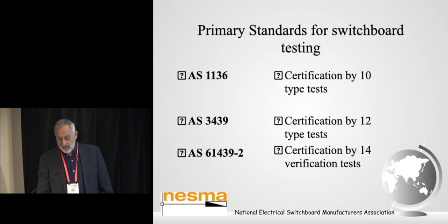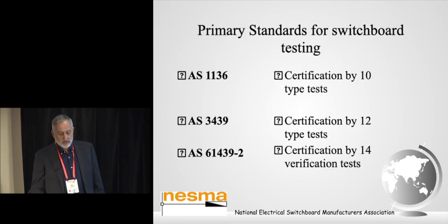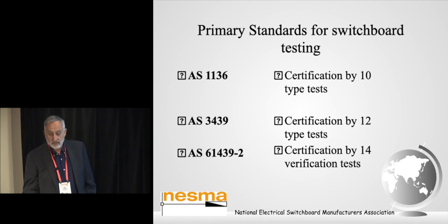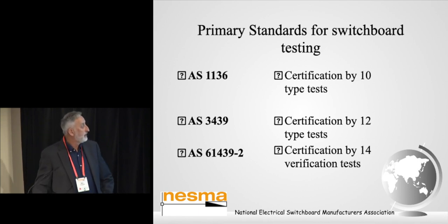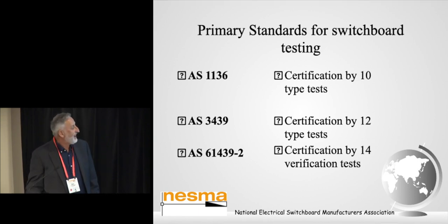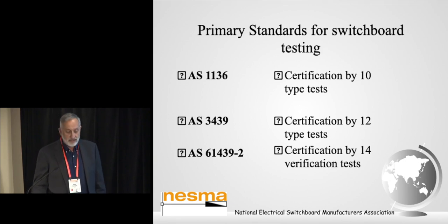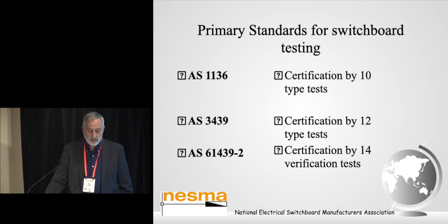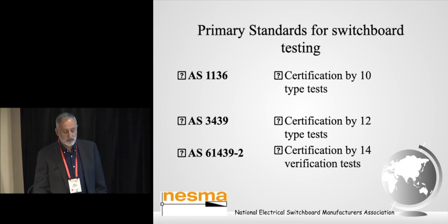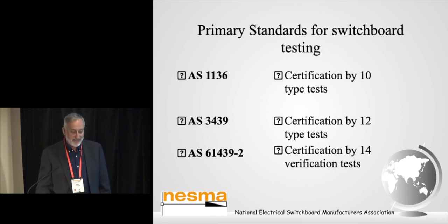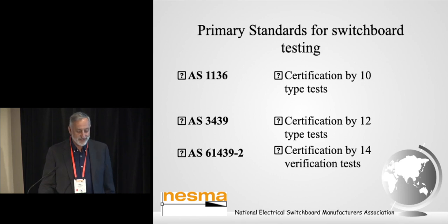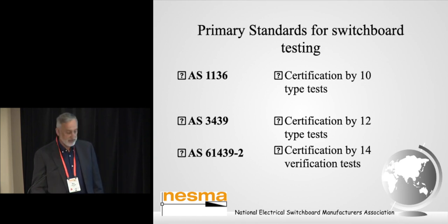So the primary standards for switchboard testing over the years have been the AS1136 that Mark would be very familiar with. We then transformed, which involved a certification by 10 type tests. We then went to the AS3439, where we also included a few additional type tests, so into 12. And then the monster standard 61439 came, where the certification was by 14 verification tests.